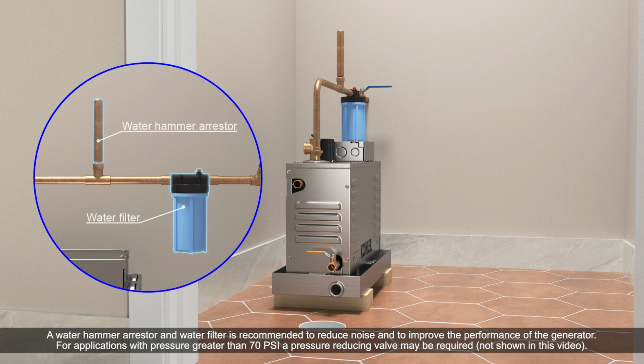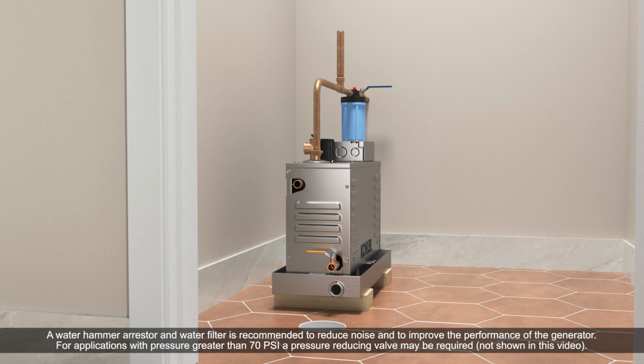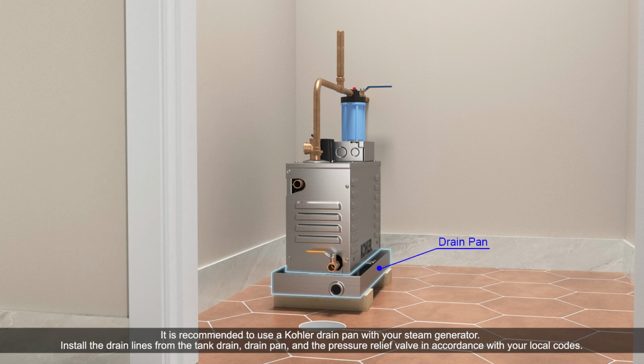A water hammer arrestor and water filter is recommended to reduce noise and to improve the performance of the generator. For applications with pressure greater than 70 psi, a pressure-reducing valve may be required, not shown in this video. It is recommended to use a KOHLER drain pan with your steam generator. Install the drain lines from the tank drain, drain pan, and the pressure relief valve in accordance with your local codes.